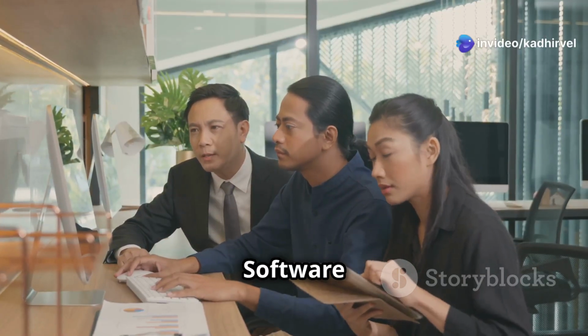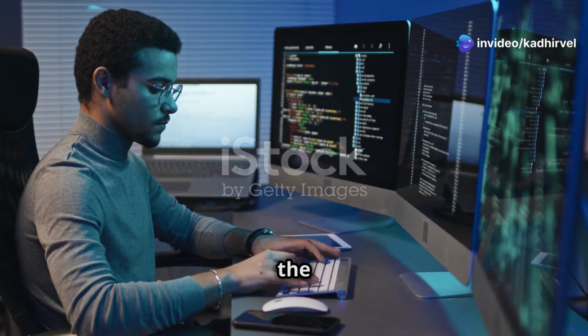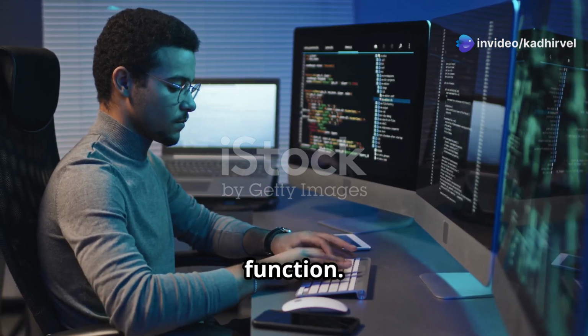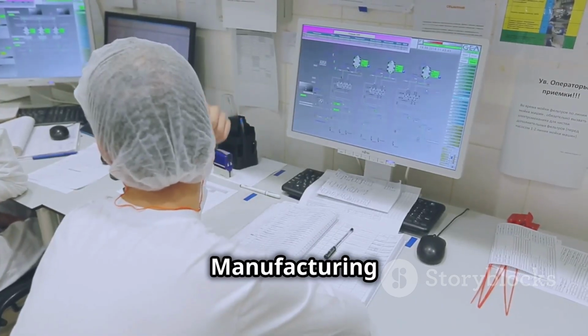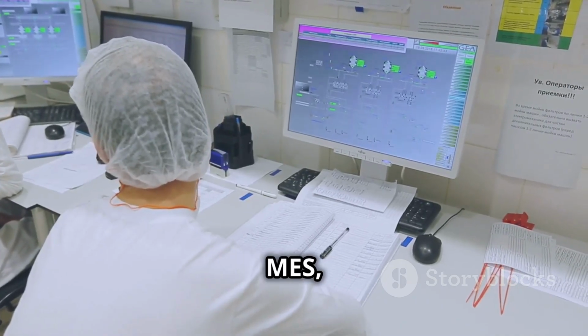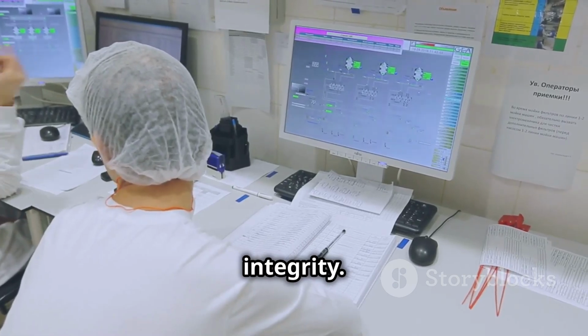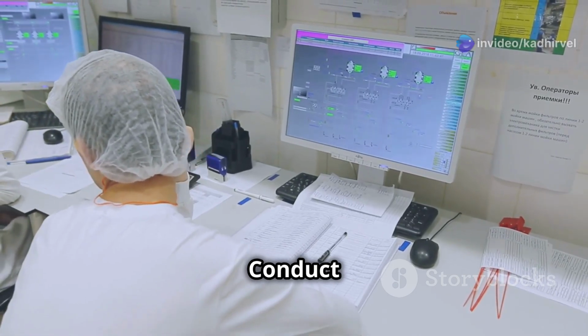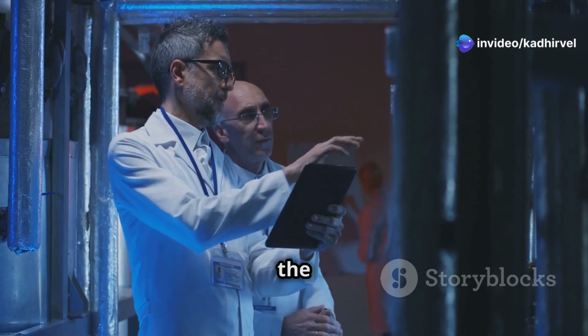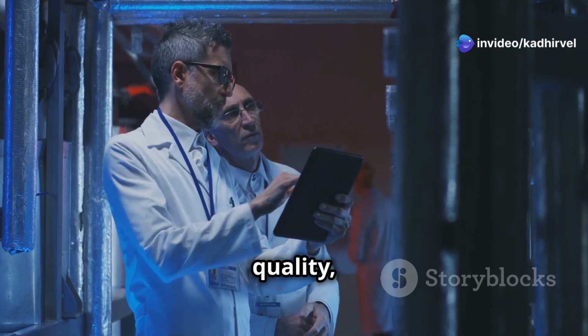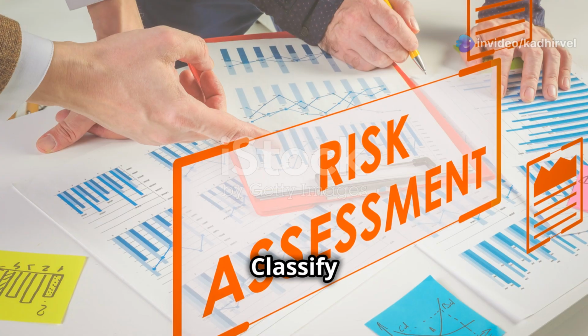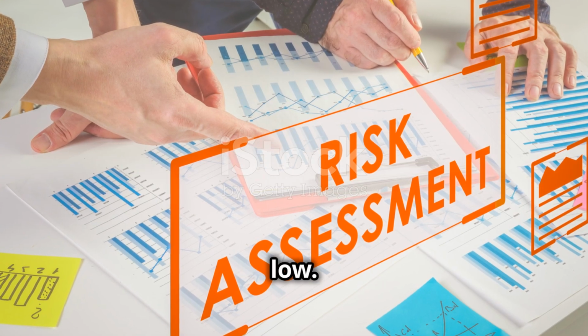First, identify the software and intended use. Define the system or software and its intended function. For example, a manufacturing execution system, or MES, that ensures batch record integrity. Second, conduct risk assessment. Identify the risks to patient safety, product quality, and data integrity. Classify these risks as high, medium, or low.